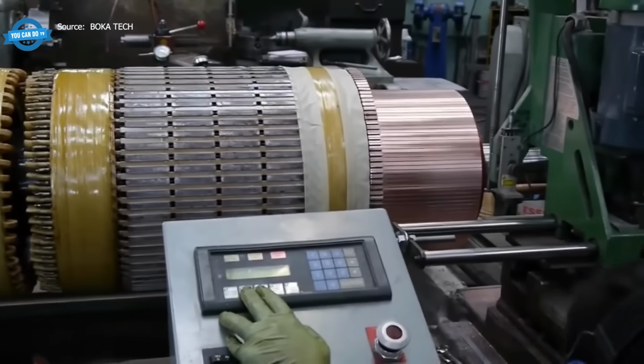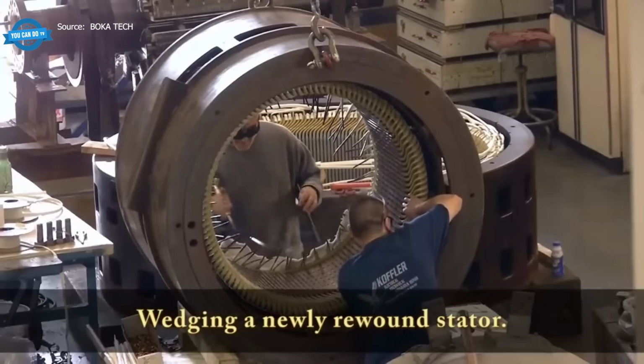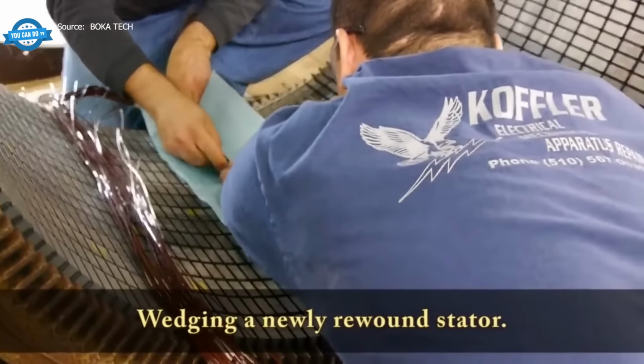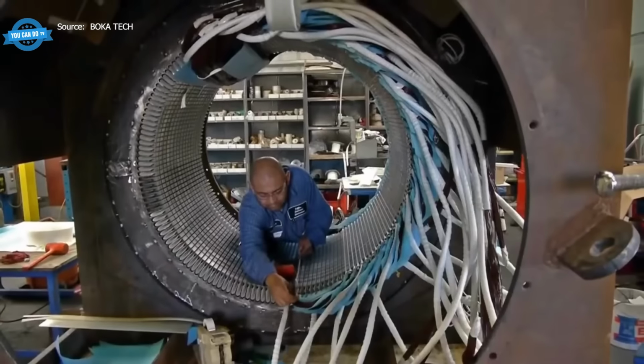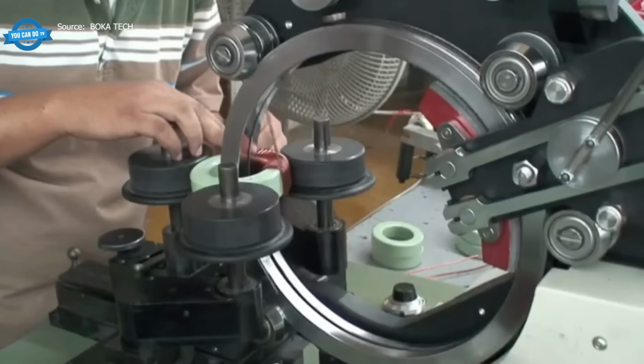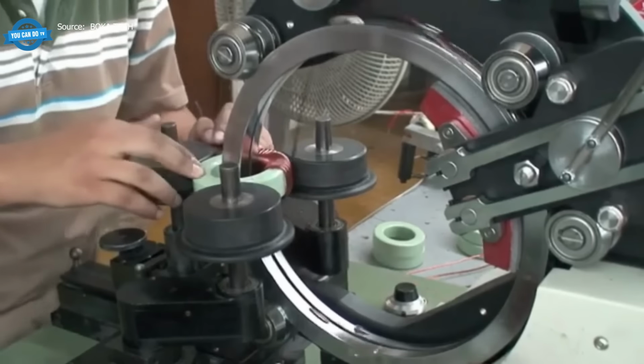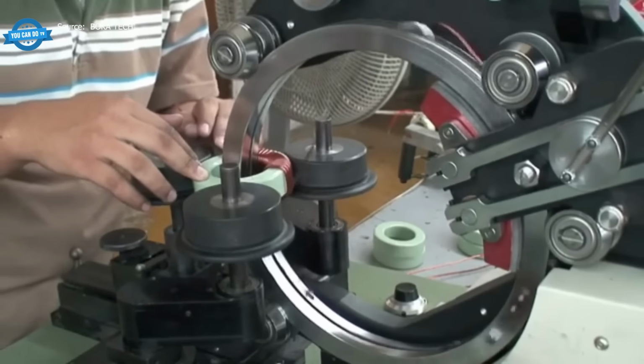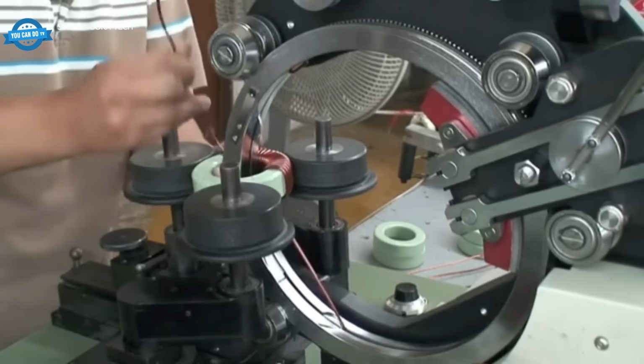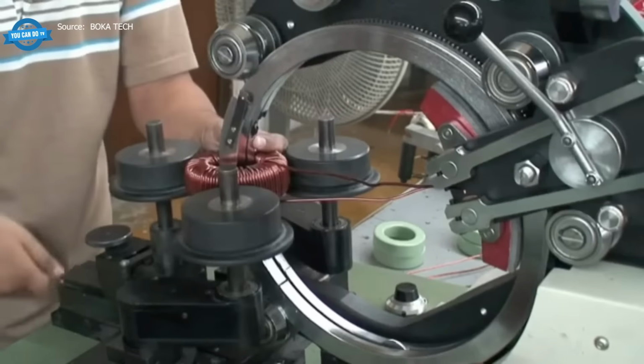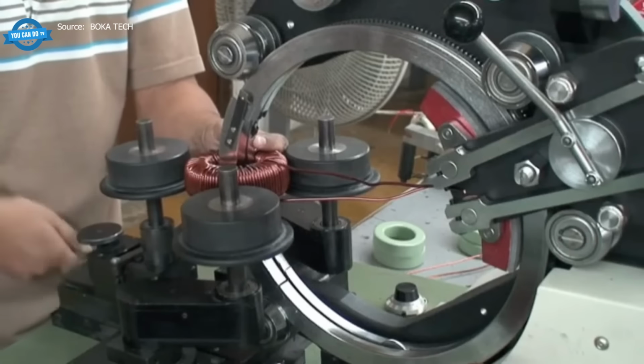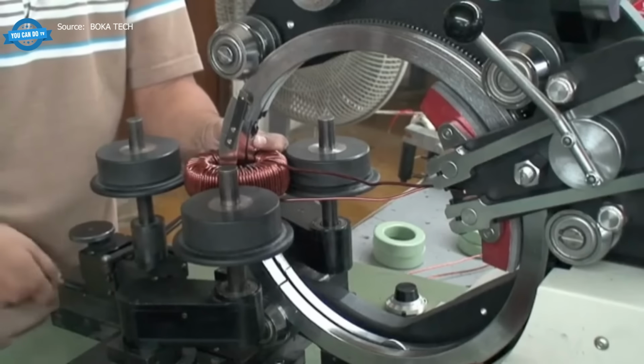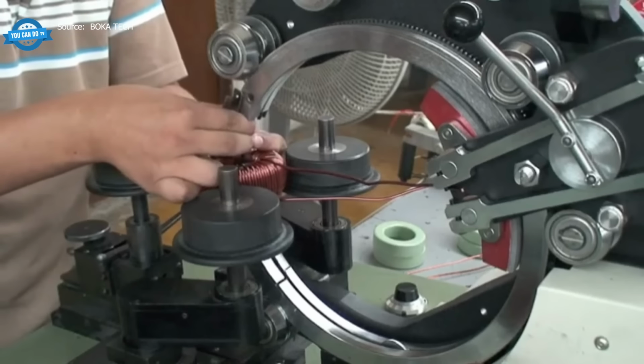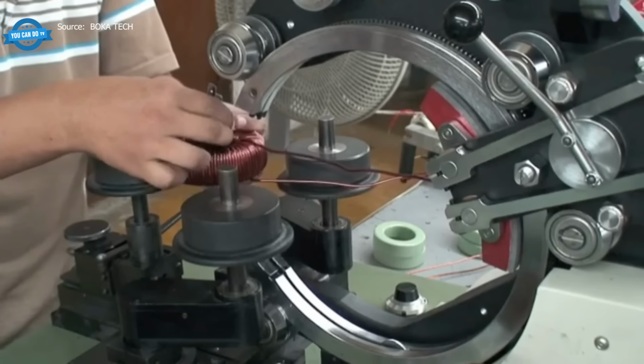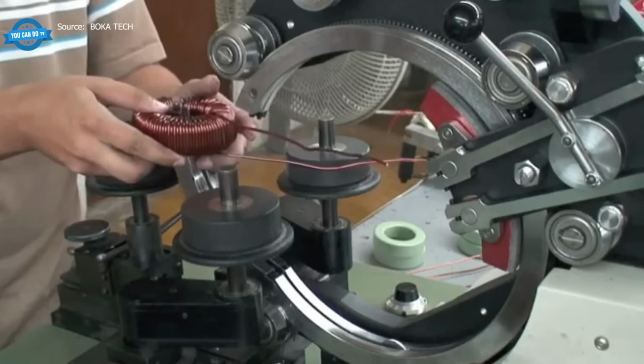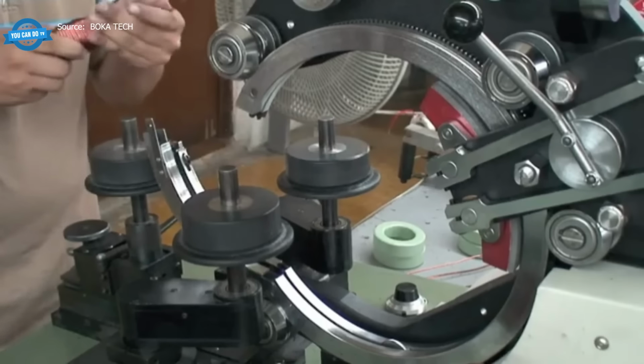Slotting wedge locks each coil into its slot mechanically after winding is complete. Toroidal winding wraps conductor continuously around a ring core, used in transformer and motor designs requiring closed magnetic paths. Each winding method creates distinct electromagnetic behavior, and an incorrect choice prevents the motor from sustaining rated load. Final inspection includes insulation testing, thermal performance evaluation, and electrical continuity checks to ensure every coil can withstand rated current, heat, and long operational duty cycles in industrial applications without failure under continuous load conditions in practice today.